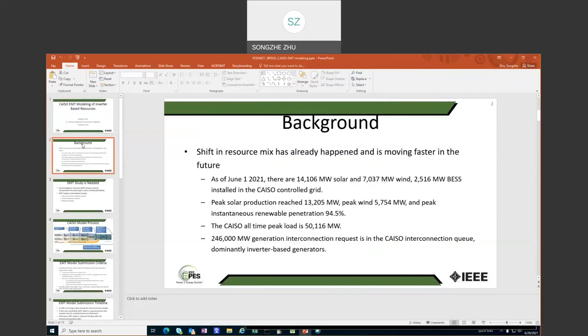First, some background. California ISO is at the front line of inverter-based resource development. In the past about 10 years, we have already seen a shift in resource mix in our grid. As of June 1st, 2021, there are already 14 gigawatts of solar, about 7 gigawatts of wind, and 2.5 gigawatts of batteries installed in our grid. Our peak solar production has reached 13 gigawatts, the peak wind production was 5.7 gigawatts, and we have reached instantaneous renewable penetration of 94.5%. So momentarily, we have been very close to 100% IBR.